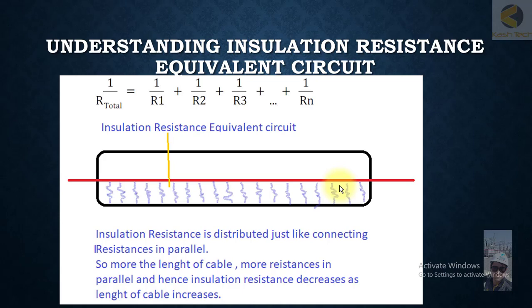And if you are testing the insulation of 500 meters or one kilometer, the insulation resistance of the longer or lengthier cable will be less based on this. So insulation is not only depending upon the material type, but also, as we can see by understanding the equivalent circuit, it's also depending on the length.